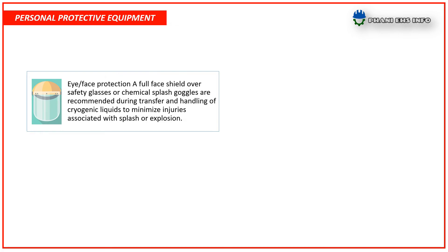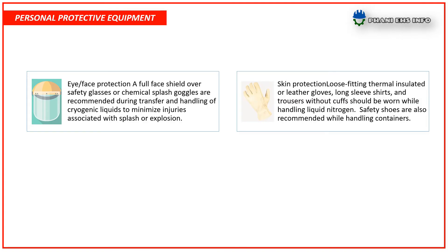Personal protective equipment to be used while handling liquid nitrogen — eye and face protection: a full face shield over safety glasses or chemical splash goggles are recommended during transfer and handling of cryogenic liquids, to minimize injuries associated with splash or explosion.